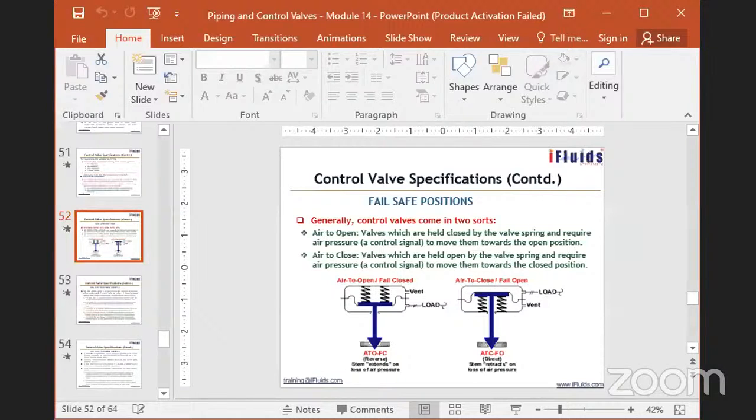You can regulate based on the inlet sensing or outlet sensing, whichever you want to control. If you want to control the inlet pressure to the equipment, then the sensing of the valve will be on the inlet side. If it is outlet pressure dependent, we will put the sensing on the outlet side. The valve will be called SAPCV. It is nothing but a valve with its own measurement and regulation. There is no separate sensor and controller, etc. These will have their own set point, their own sensing. Everything is contained in the valve. So these are called self-actuating valves.